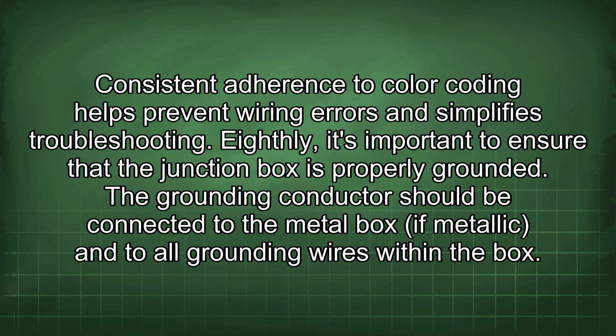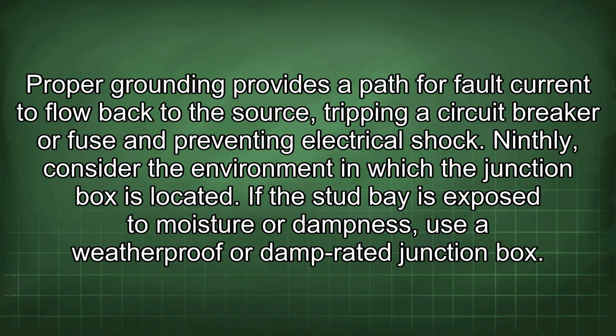Eighthly, it's important to ensure that the junction box is properly grounded. The grounding conductor should be connected to the metal box if metallic and to all grounding wires within the box. Proper grounding provides a path for fault current to flow back to the source, tripping a circuit breaker or fuse and preventing electrical shock.